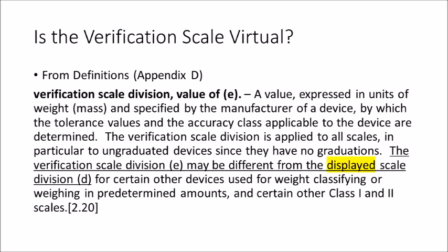And finally, the verification scale division may be different than the displayed scale division. Now, why is the word displayed here? Because the verification is declared. It's not displayed.